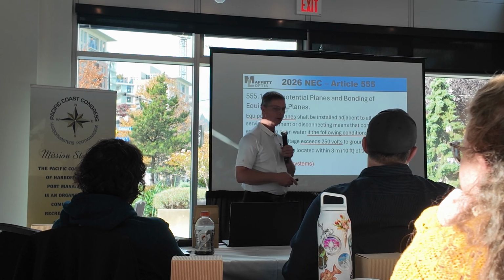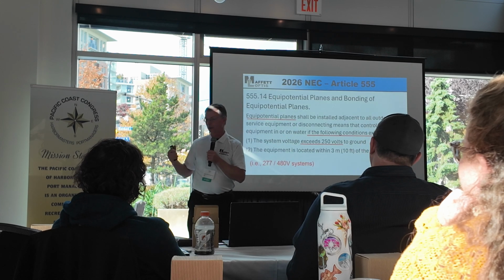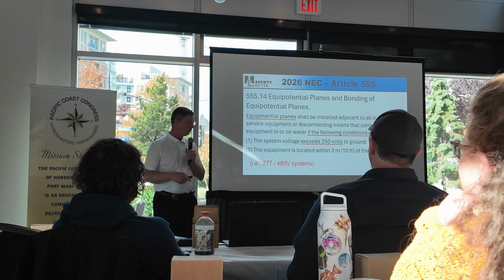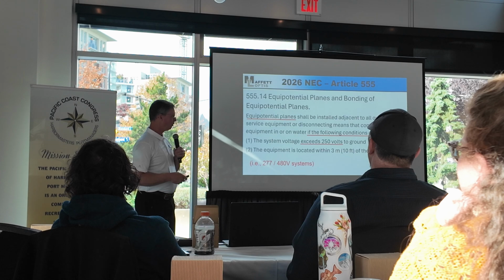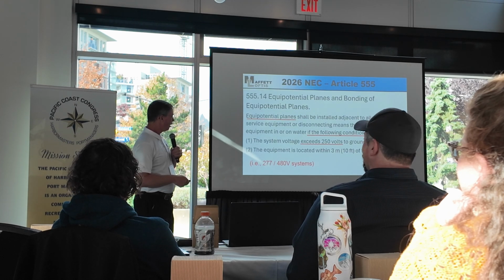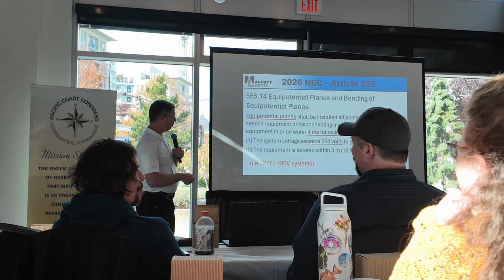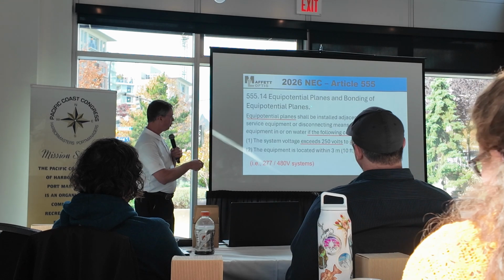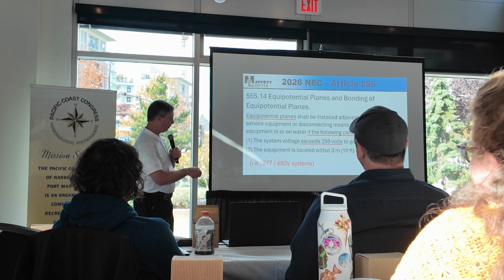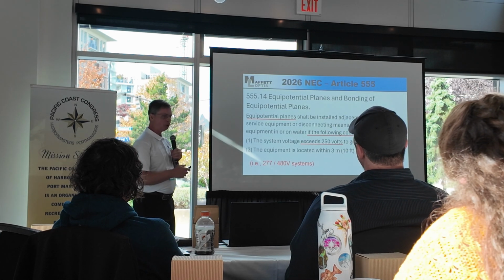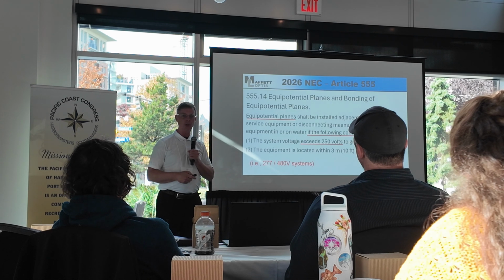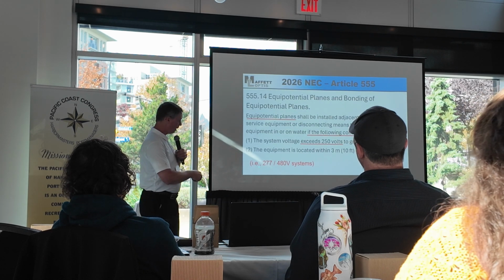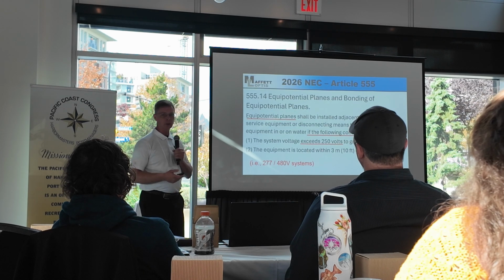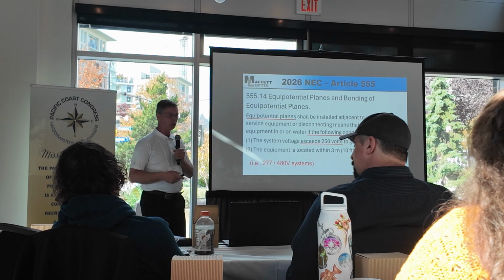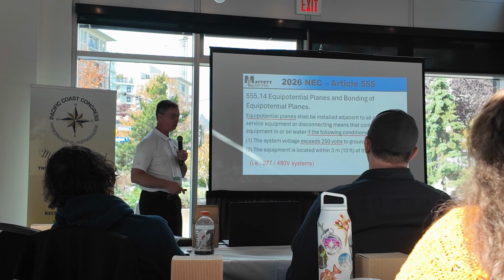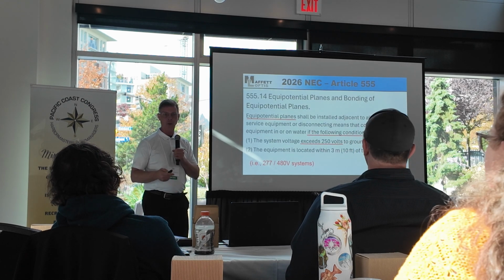feet of the water. So both of these conditions have to be true to be able to do this equipotential plane. And if these are not true, then you don't have to do it. That's what I suggest. Many of the systems I design are 480 systems, and there are many 480 systems out there. Just don't install it within 10 feet of the body of water, and you don't have to do this.